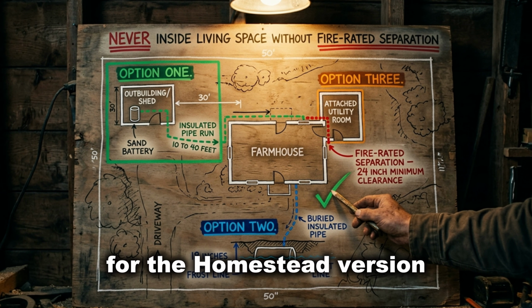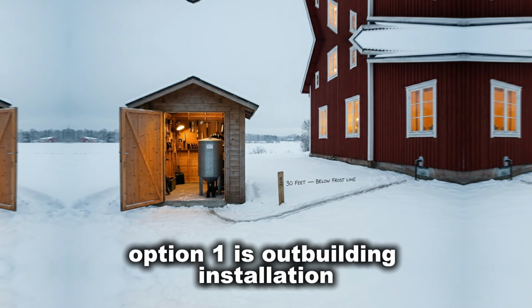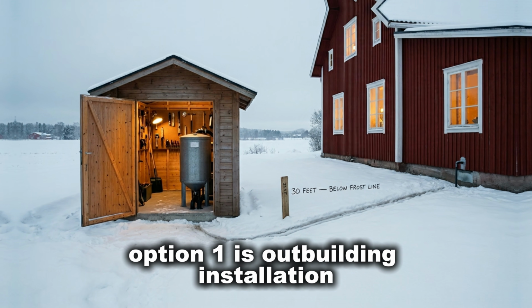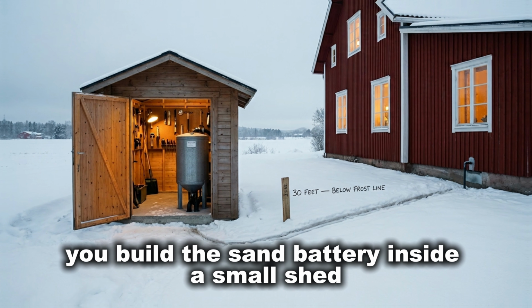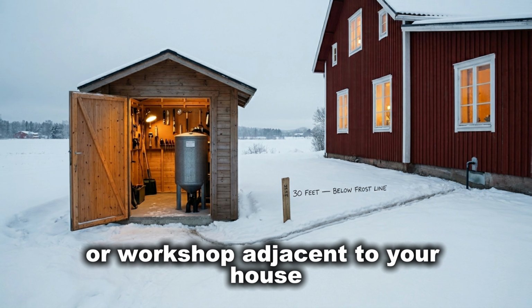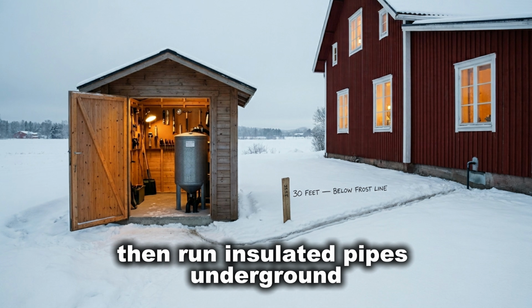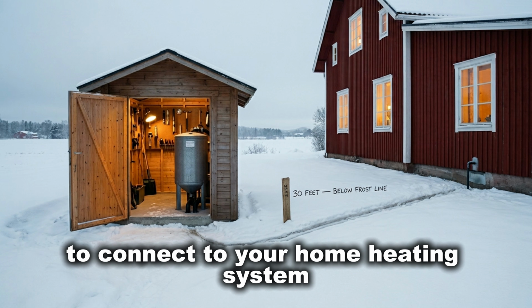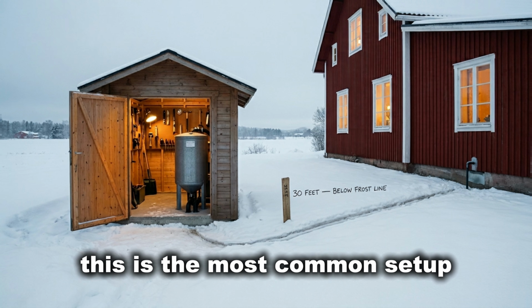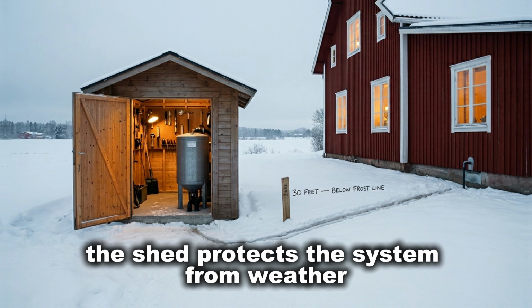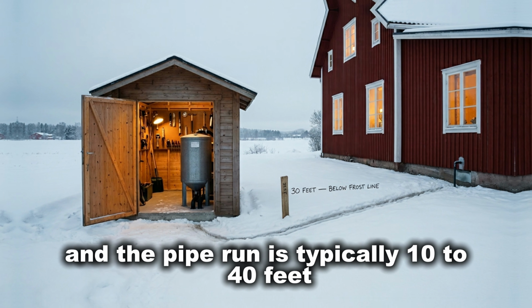For the homestead version, you have 3 options. Option 1 is outbuilding installation. You build the sand battery inside a small shed or workshop adjacent to your house, then run insulated pipes underground to connect to your home heating system. This is the most common setup. The shed protects the system from weather, keeps it accessible, and the pipe run is typically 10 to 40 feet.